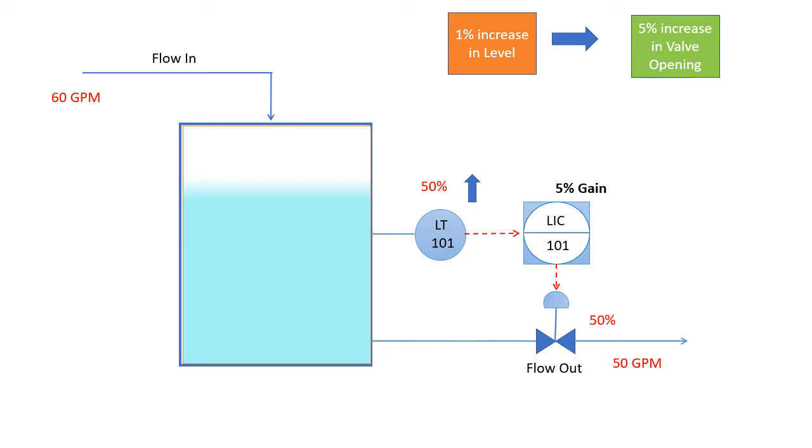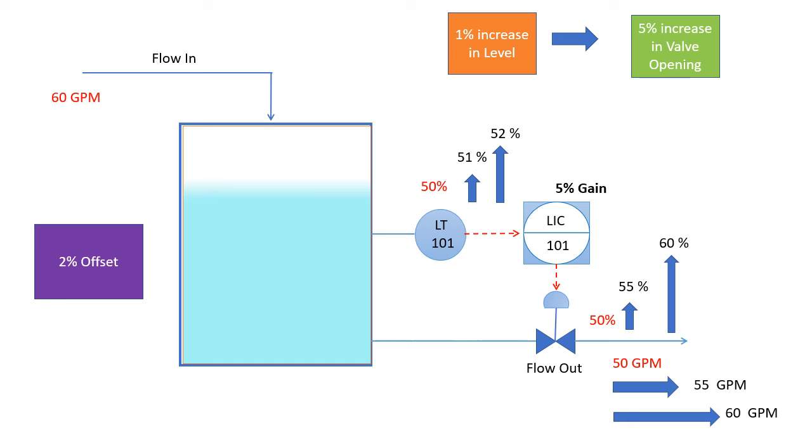So if the level rises to 51 percent, the valve opening will increase to 55 percent leading flow to 55 GPM. If level further raises to 52 percent, the valve opening goes to 60 percent, leading flow to 60 GPM. At this moment, inlet flow equals outlet flow, so there is no further change in level. Now level is stuck at 52 percent. So in this case, we have an offset of 2 percent.